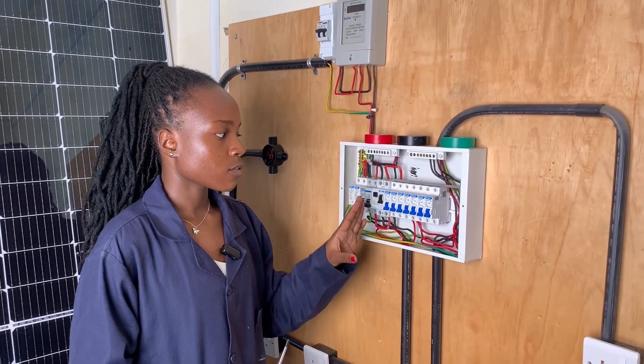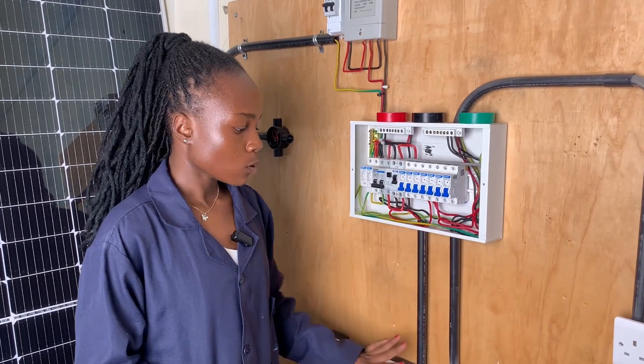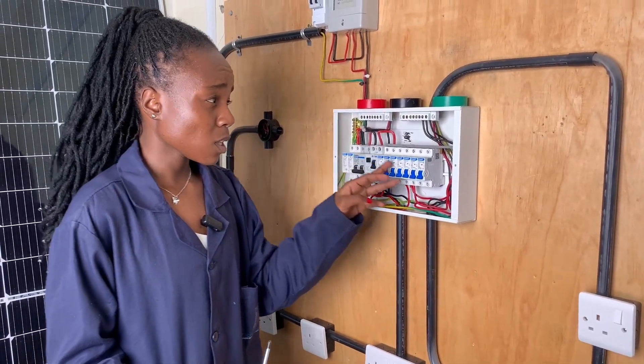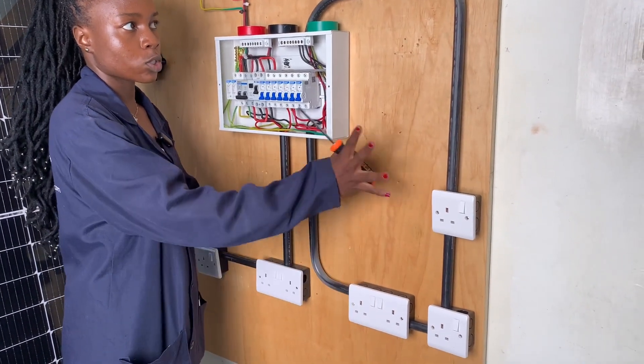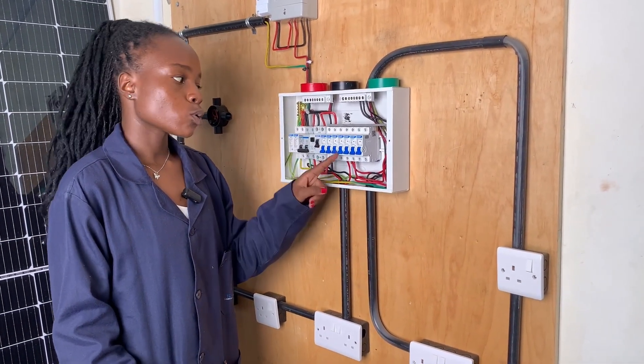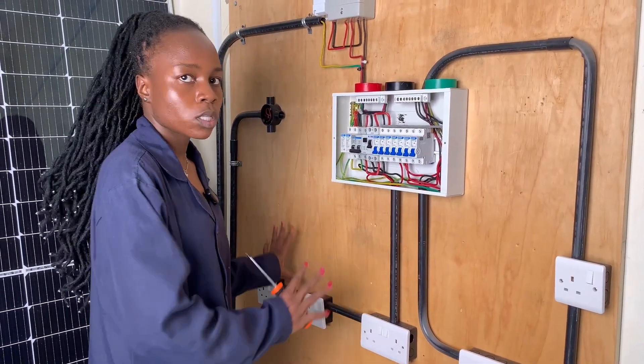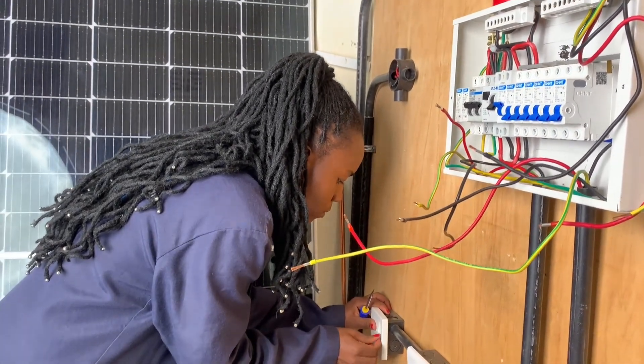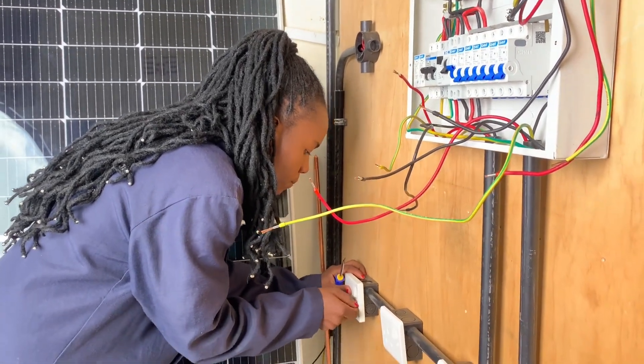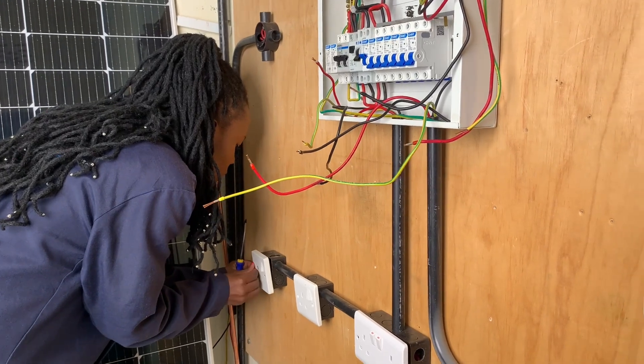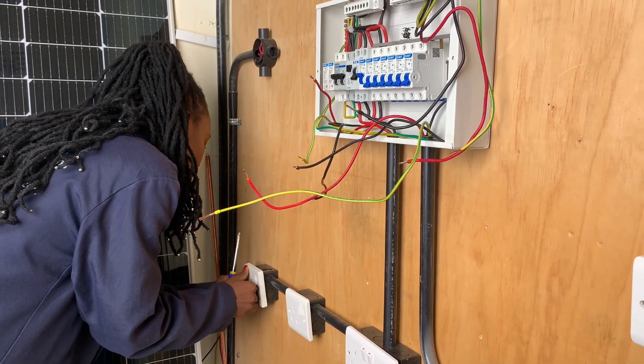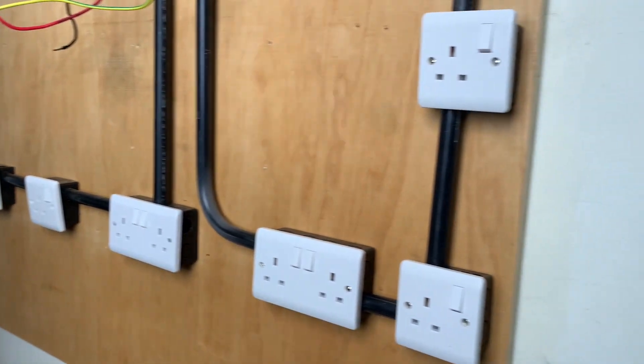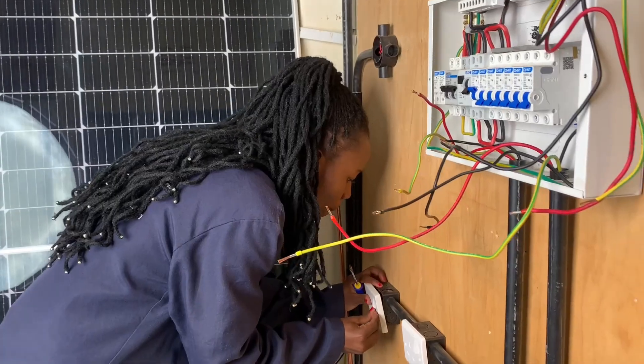On this consumer unit, we have different amperes. For these sockets, we have two circuits: the ring and the radial, each served by a 20-ampere MCB. For a radial circuit, it starts from the consumer unit and goes to the first socket, then the second, and finally the last. For a ring circuit, it starts from the consumer unit, goes to the first socket, loops through the second, third, fourth, and however many sockets are on the circuit, then goes back to the consumer unit — making a ring.